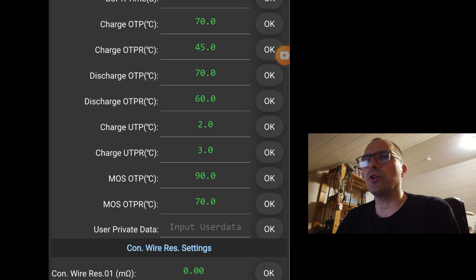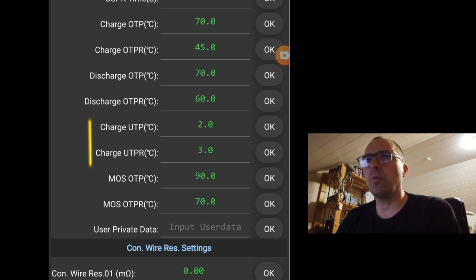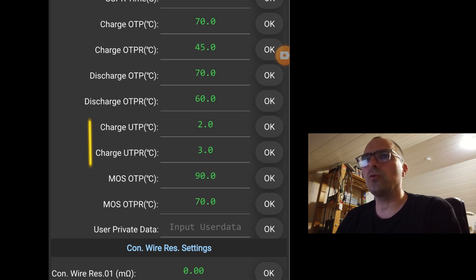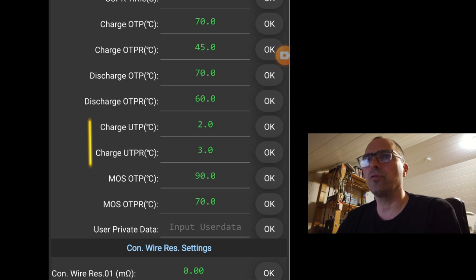Charge under voltage temperature protection. We can't use LiFePO4 below 0 degrees. So we have a small margin. When temperature goes below 2 degrees, I will not allow to charge the batteries. I will allow again when the temperature rises above 3 degrees. That's the charge under voltage temperature recovery.